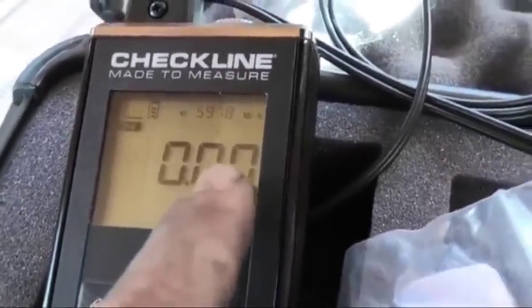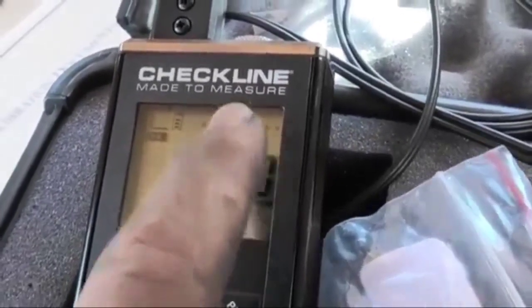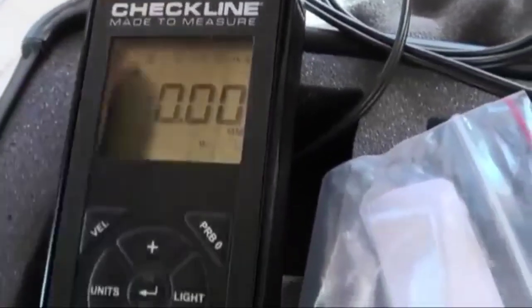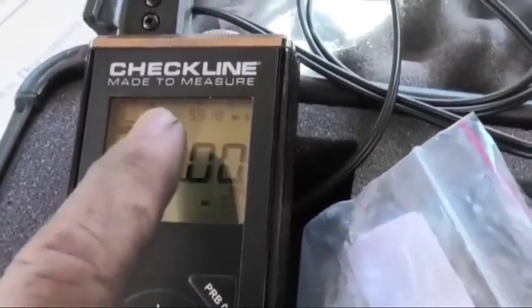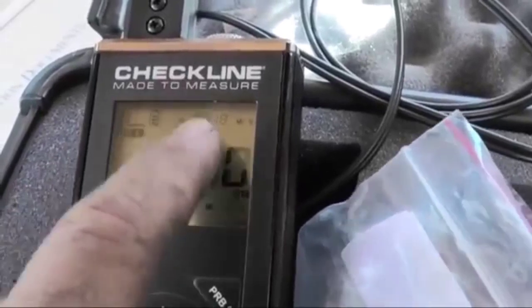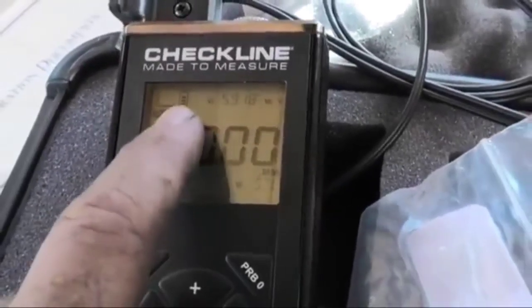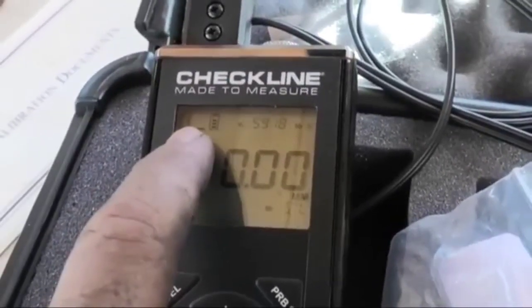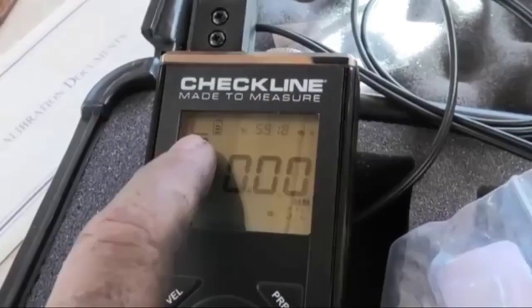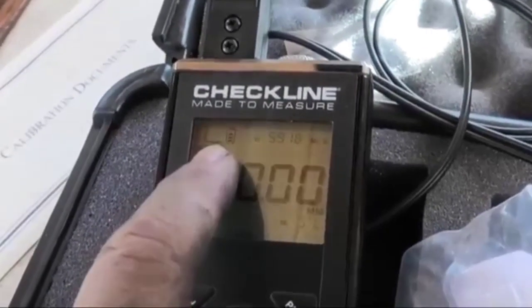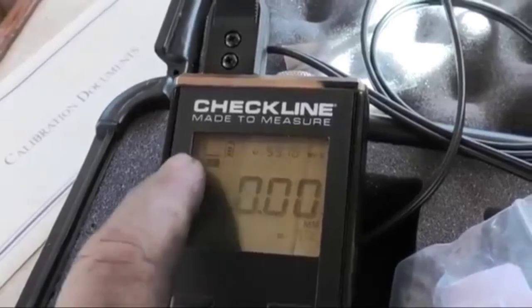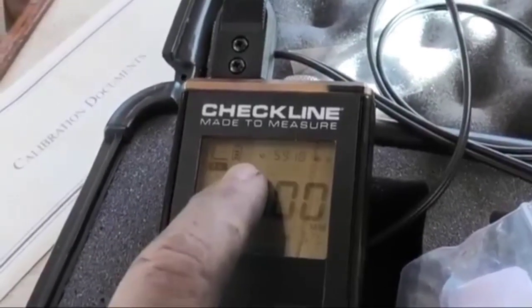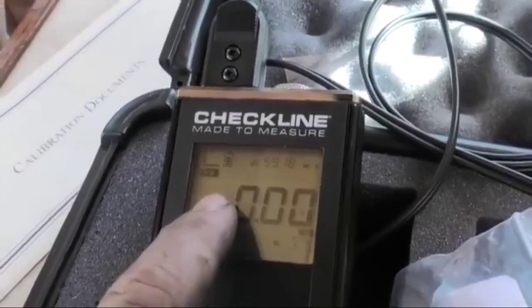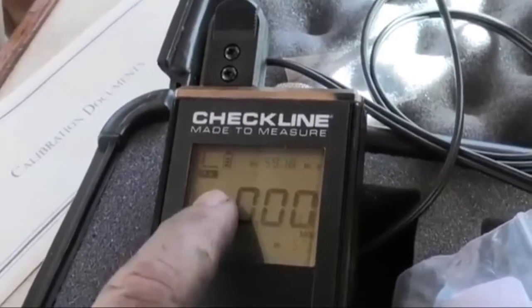4340, and this isn't adjustable on this unit, but if it was an adjustable unit, Checkline make a huge range of these units, then you need to make sure you've got the right velocity for the material you're measuring. Here we've got a battery level, and then these markers to the left here are saying how often the unit is getting the same reading over and over. So if you get all 6 bars, it means it's getting a very consistent reading, which means you can have a high confidence in that reading.